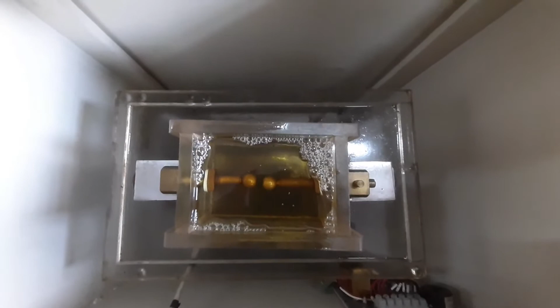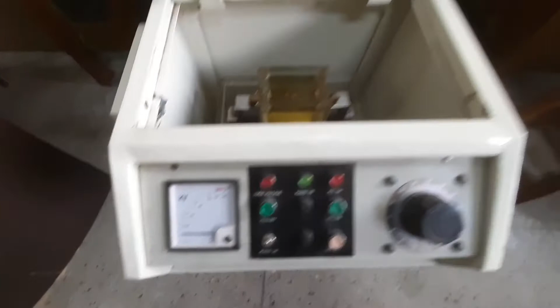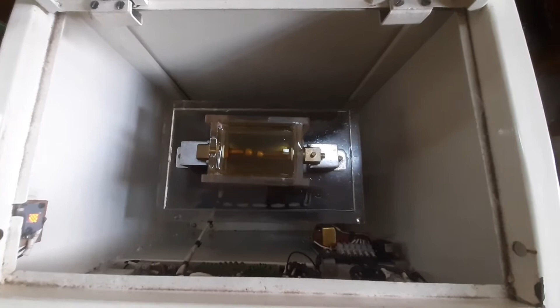They are separated by a 4 mm distance, and we will apply electrical pressure through the electrodes in the liquid dielectric material. We can apply up to 90 kV voltage between the two electrodes, and we will observe when the oil is punctured, meaning its dielectric strength breaks down.